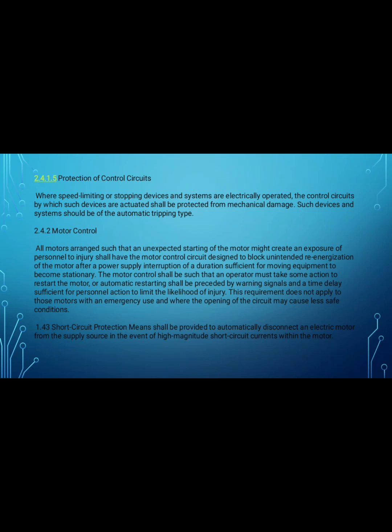These requirements do not apply to those motors with an emergency use and where the opening of the circuit may cause a less safe condition. A motor control refers to the system or method used to operate, regulate, and manage the performance of an electric motor. 1.43 Short circuit protection means shall be provided to automatically disconnect an electric motor from the supply source in the event of high magnitude short circuit current within the motor.